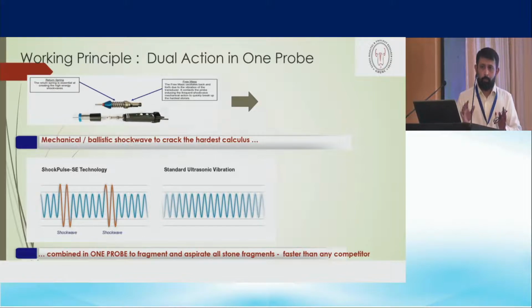Now, coming to the principle of this machine, it produces continuous ultrasonic waves at a very high frequency of 20,000 hertz. Along with that, it produces an intermittent ballistic component, a pneumatic component, which creates a hard hit on the stone so that the fragmentation becomes faster. And it is a proprietary technology which they have not disclosed to others.